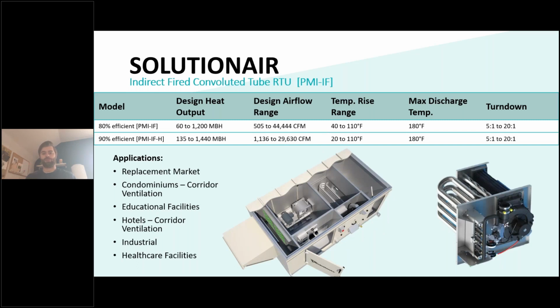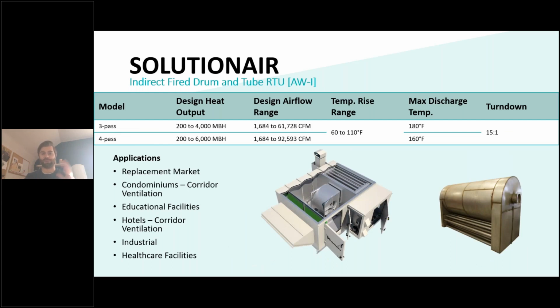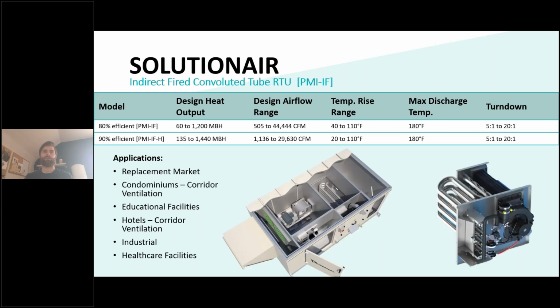For the convoluted tube heat exchanger, we have 2 options here. I'll start with the 80% efficient. So typically we see a convoluted tube. The choice to go in that direction rather than a drum and tube is typically just on the small end of the units. So the design heat output has a much lower initial limit. So 60 MBH in this case. The drum and tube had 200 as its minimum, to give you a bit of an idea. As well as the design airflow are much lower. So with the 80%, we can go down to 500 CFM, all the way up to 44,000.